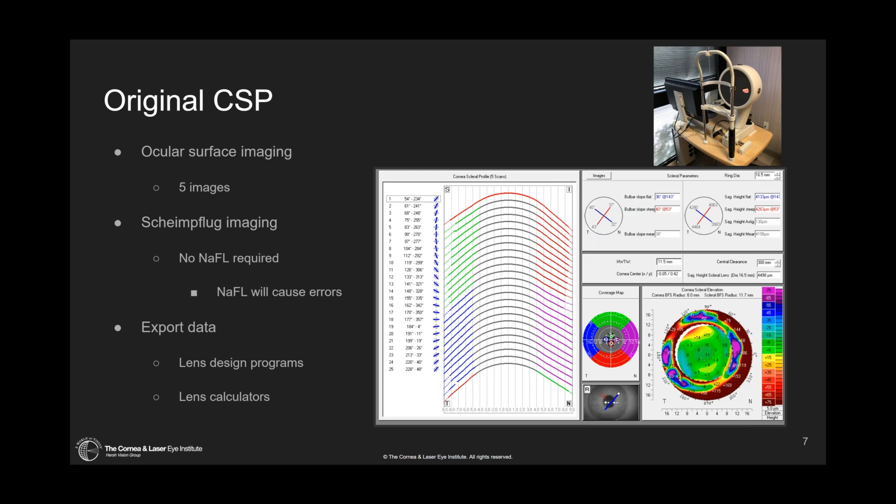The system uses a Scheimpflug camera as its main sensor, taking slices of the cornea and recreating those into a three-dimensional object. With the original CSP — which stands for corneal scleral profile — they used the Scheimpflug camera and extended the sensor images out onto the sclera and overlying conjunctiva, capturing images to produce a much wider surface scan of about 16 to 17 millimeters.